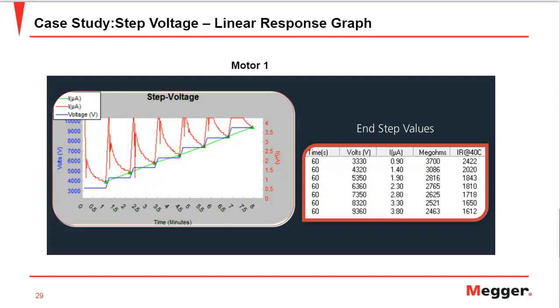by comparing the change in leakage current between each step. So here you see, and this is motor 1, the leakage current calculated in the first step, and the difference between the first and second, or the further next step, is 0.5 microamps, which is constant. There could be some change here of around 0.40 microamps, which is still under the standard. And this is how the graph would look.